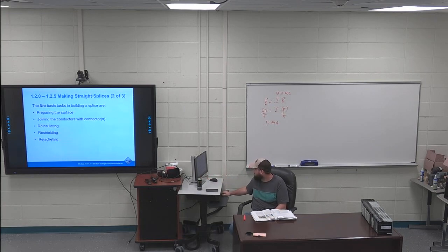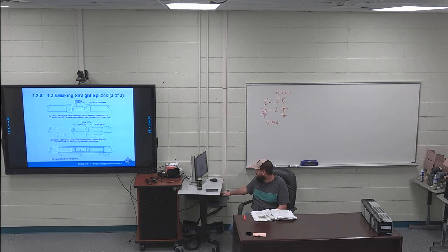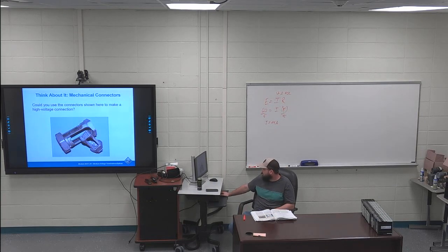Moving on to 122. Joining the conductors with connectors. Page 7, I've got the third full sentence on page 7, or second to last sentence of that started paragraph, highlighted. The suitable connector for medium voltage cable splices is a compression type or crimp type. So you're not using the split bolts. Do not use split bolts for this. Can you use that connector?